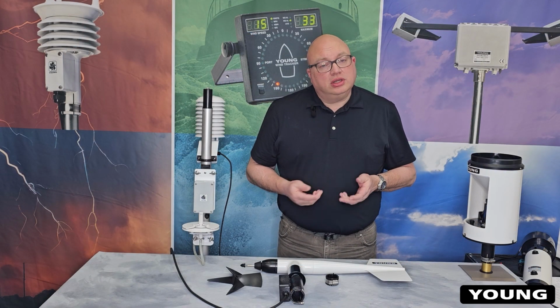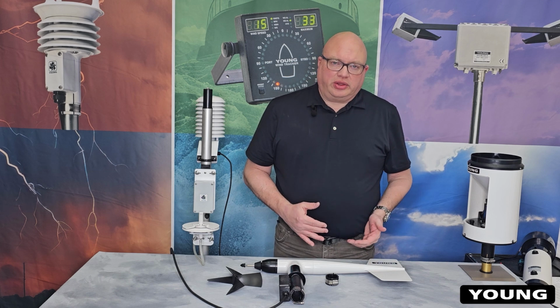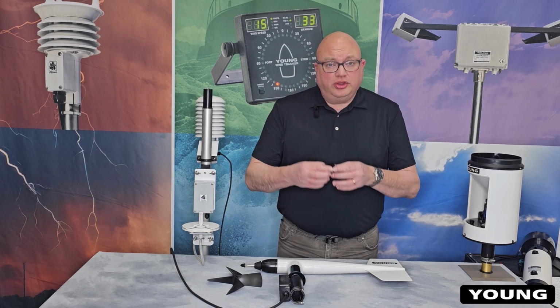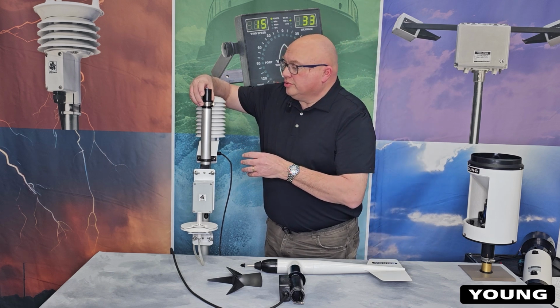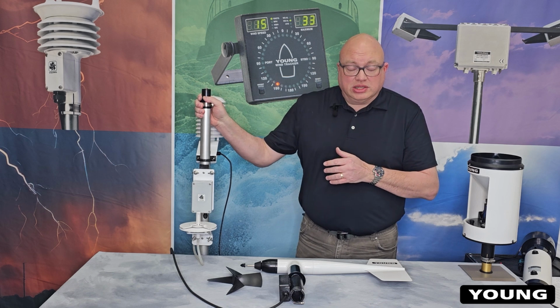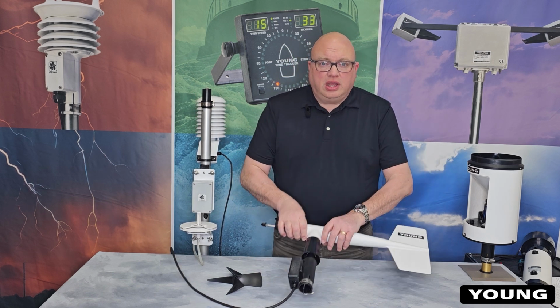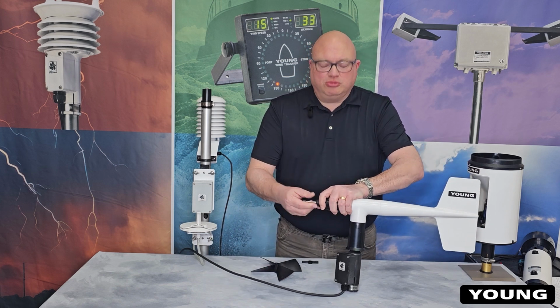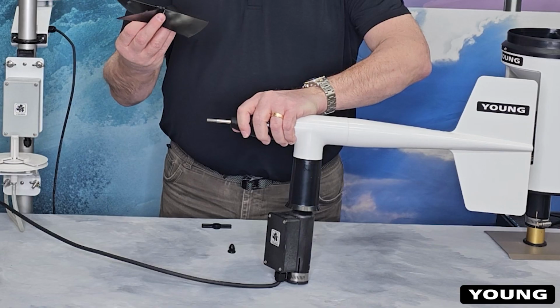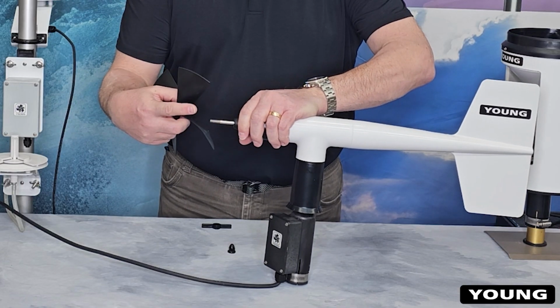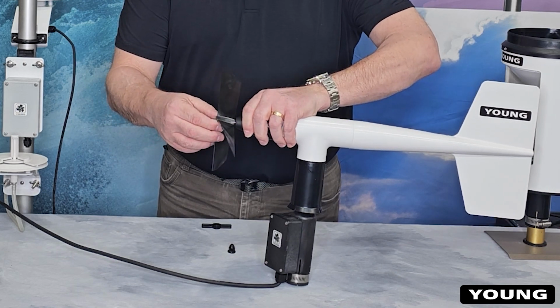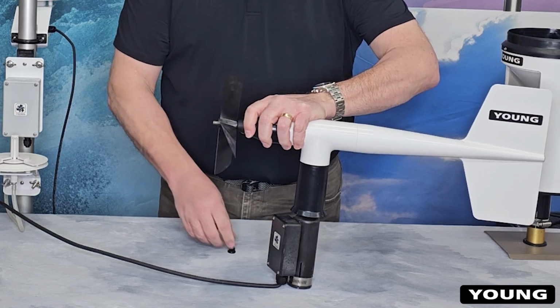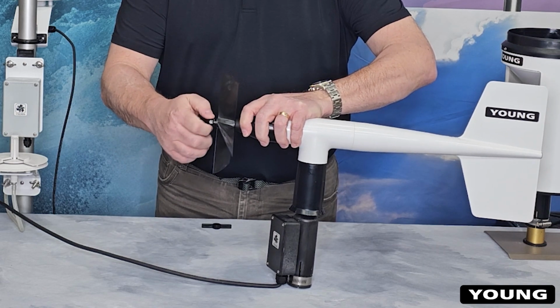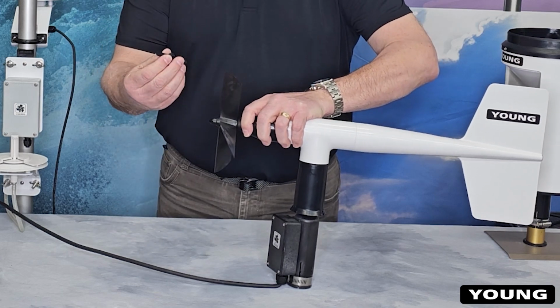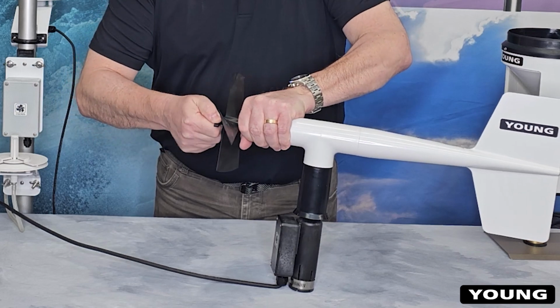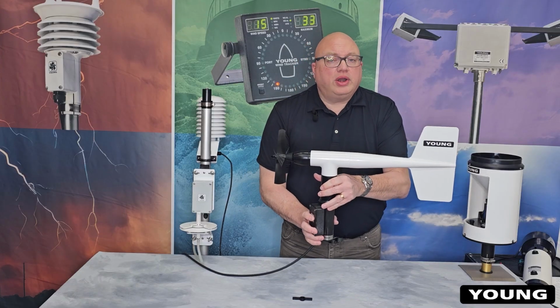The next instrument we're going to install is our wind monitor. You'll need some preparation before you can install it on the mast. The first thing you'll need to do is make sure that you install the orientation ring on the mast. You don't need to tighten this just yet, you just need to make sure it's installed. As for the wind monitor itself, it comes, for its protection, with the propeller removed. To install it, remove the propeller nut. Install the propeller with the notched end towards the instrument and make sure that you index it into the propeller shaft. Once the propeller is installed, install the propeller nut and tighten with our included wrench. Now you're ready to install the wind monitor on the mast.